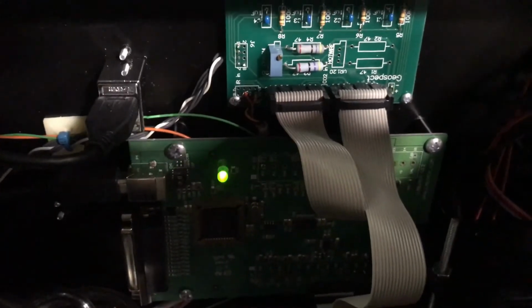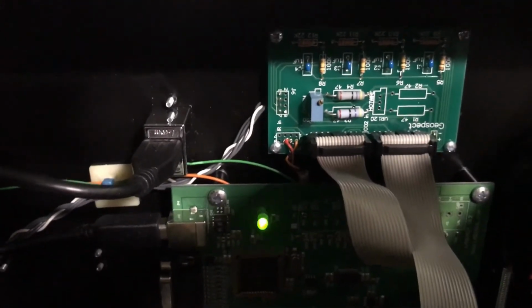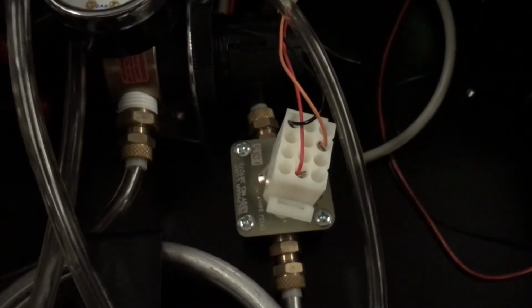On the inside, you have your data acquisition board that's flashing. This is just a special Geospect board that it hooks to. Your sample pump, power supply, infrared chamber, chromatograph column, and your filament chamber for the chromatograph.